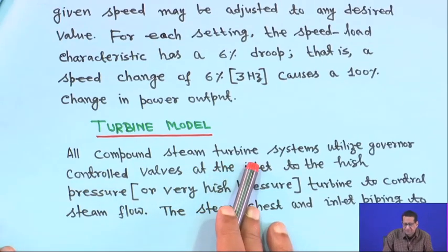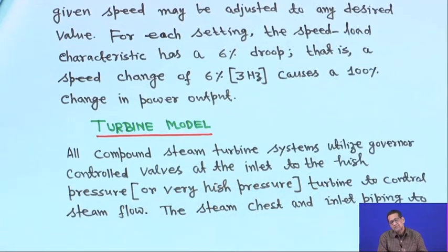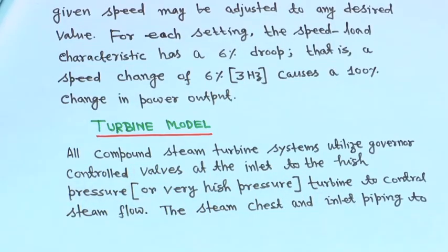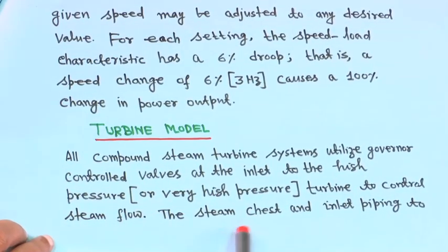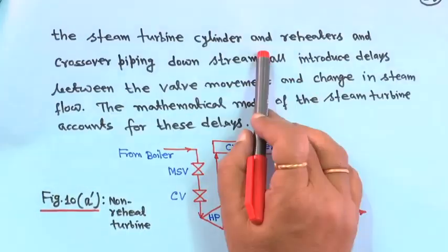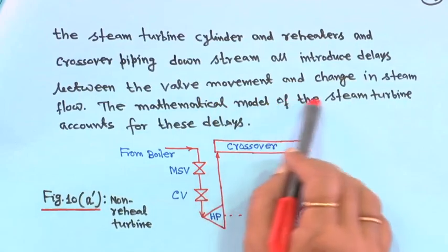All compound steam turbine systems utilize governor control valves at the inlet to the high pressure or very high pressure turbine, because a turbine has different sections: high pressure, intermediate pressure, and low pressure. We will represent them using Laplace transform and block diagram representation. The valve mechanism for a steam turbine has different sections, and for simplicity we will take the simplest model. The steam chest, inlet piping, reheaters, and crossover piping all introduce delays between valve movement and change in steam flow.